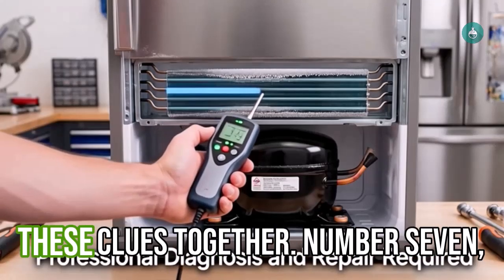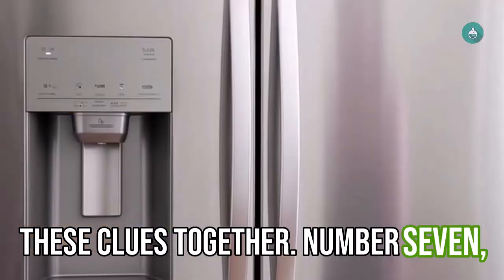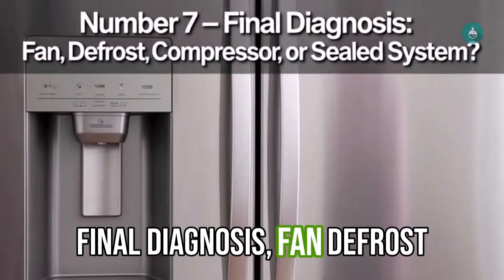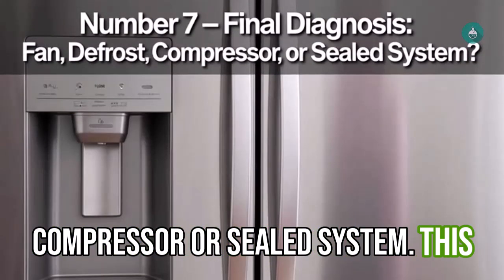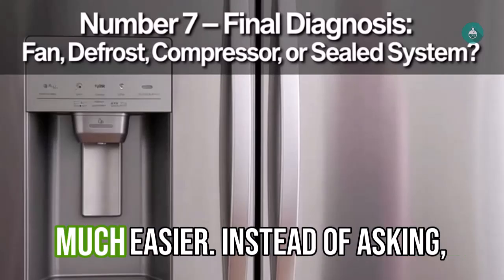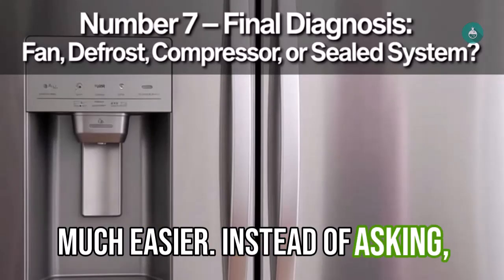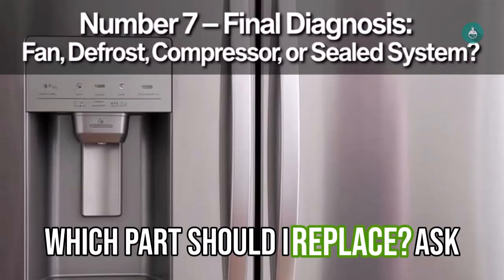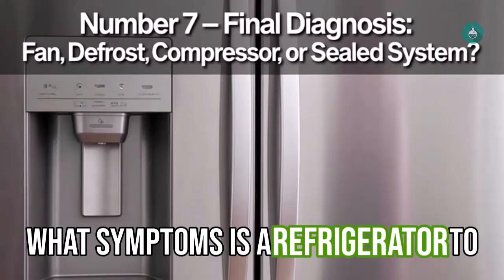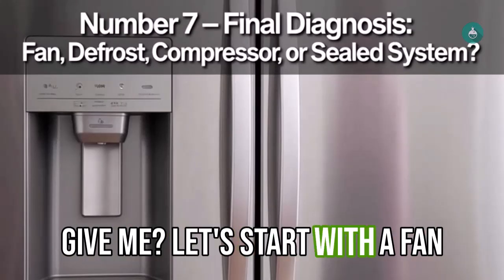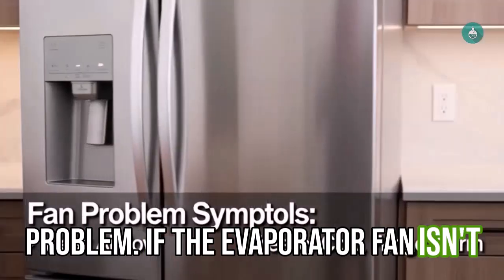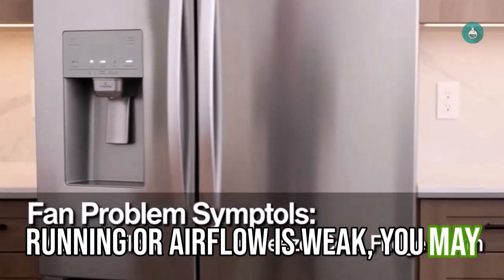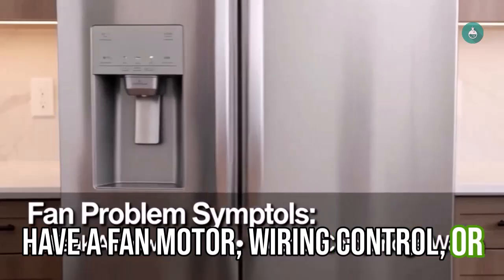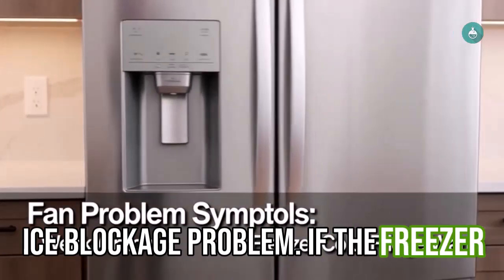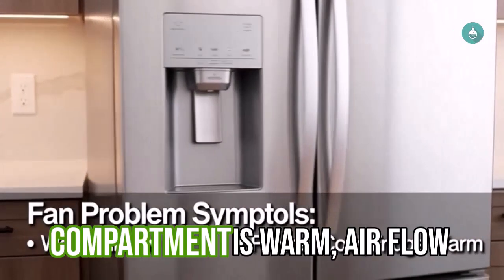So now let's put all of these clues together. Number 7, final diagnosis: fan, defrost, compressor, or sealed system. This is where troubleshooting becomes much easier. Instead of asking, which part should I replace? Ask, what symptoms is the refrigerator giving me? Let's start with a fan problem. If the evaporator fan isn't running or airflow is weak, you may have a fan motor, wiring control, or ice blockage problem. If the freezer is cold but the refrigerator compartment is warm, airflow becomes especially important.